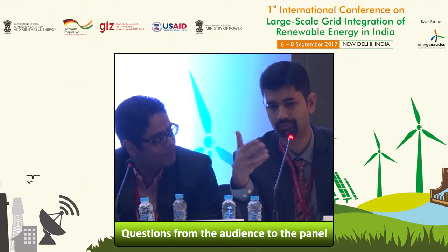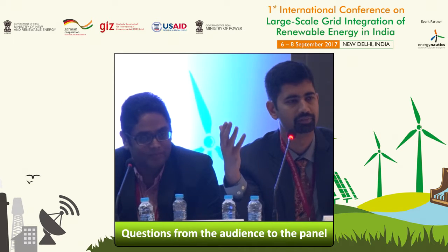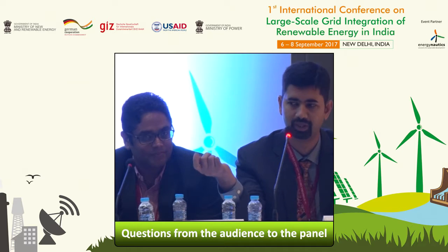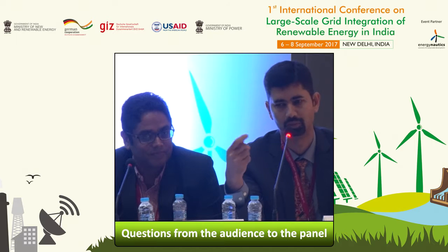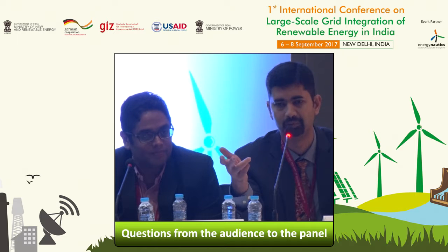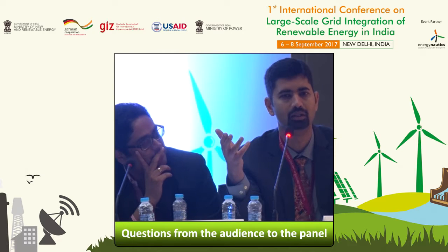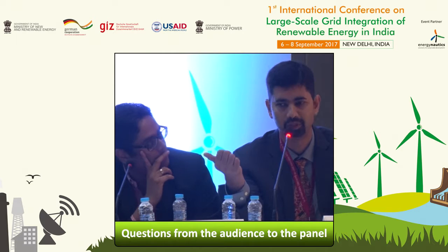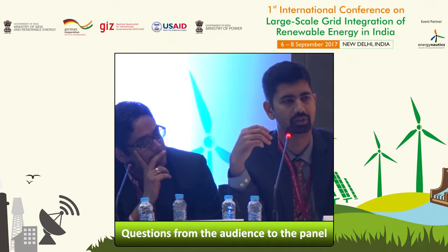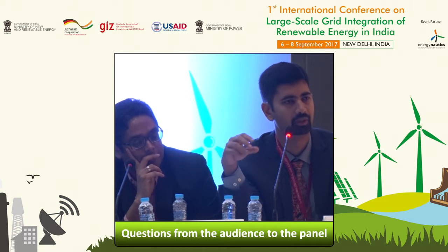Let's say it's a group of 15,000 megawatts of wind interconnecting, and there's multiple, say, 345 kV transmission lines going on. So clearly, not only are those lines going to benefit the new wind resources, but it's also going to help from a load serving perspective. It's going to help from a market efficiency perspective, might help with some compliance obligations through NERC and so forth. So it's a fairly broadly required transmission facility, with multiple beneficiaries spread across time, spread across geographical jurisdictions. So those costs are then prorated across the footprint because there are multiple beneficiaries.